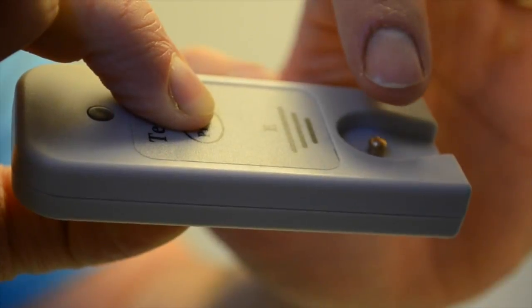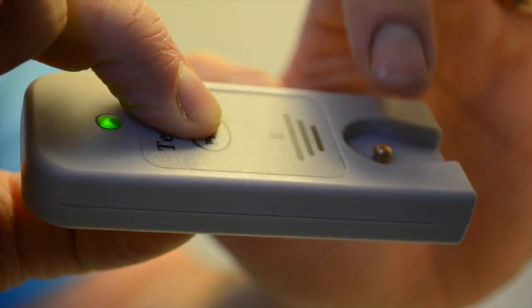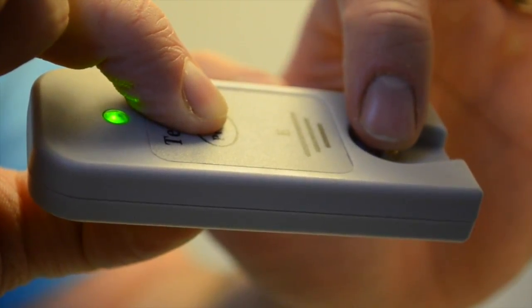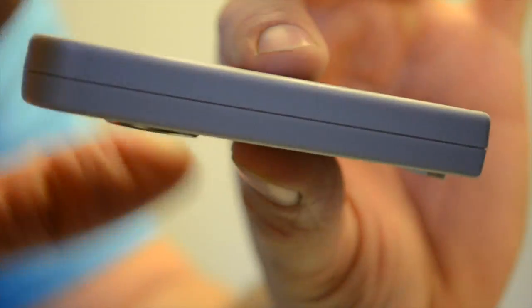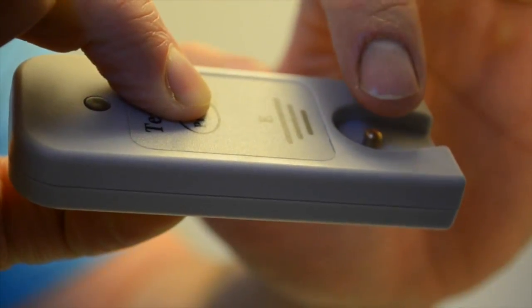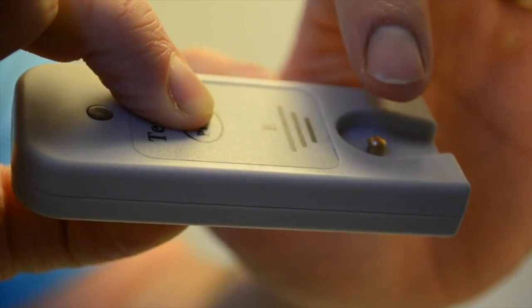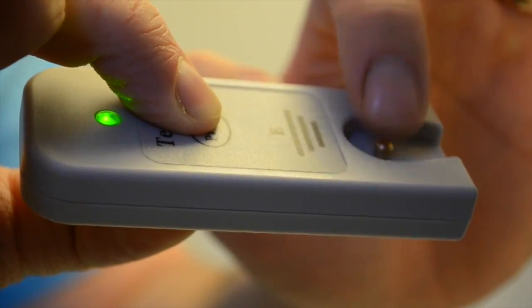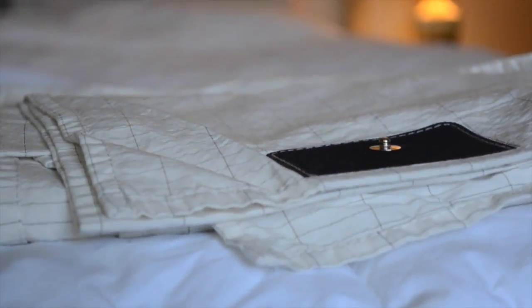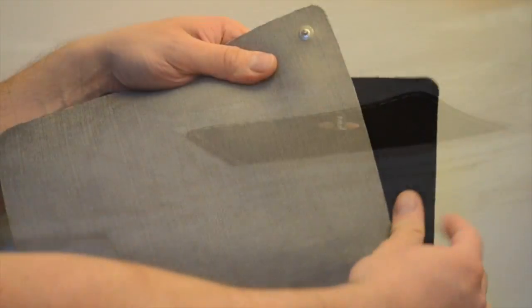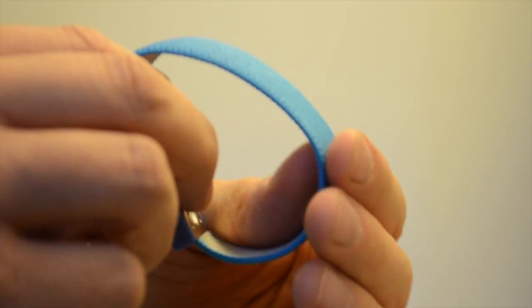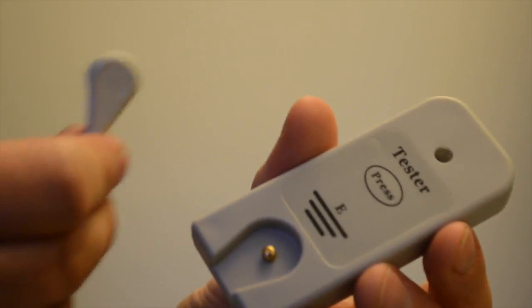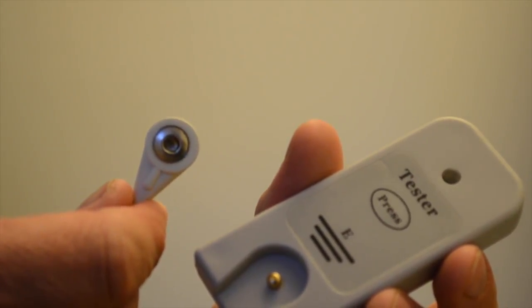With a finger on your other hand, touch the connection on the top side of the tester while still holding the button down and your thumb on the watch battery. The green light will come on when you touch the top side connection because you have completed the circuit. Once you verify the tester is functioning, you'll test all parts of the earthing system in a similar way by adding them into the circuit as you did to check the tester. Start with the grounding cord that you are using.